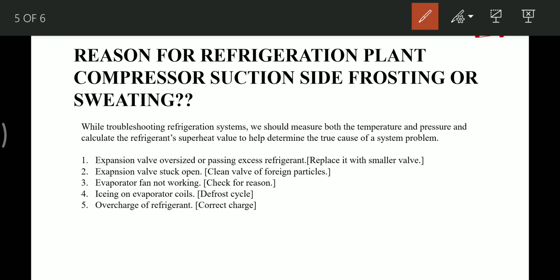So just looking at the frost or the sweating on the suction side, we cannot tell that the system is not performing properly. But after checking the superheat value, we can say the system is not functioning properly if the superheat value is not equal to the specified value of the manufacturer.